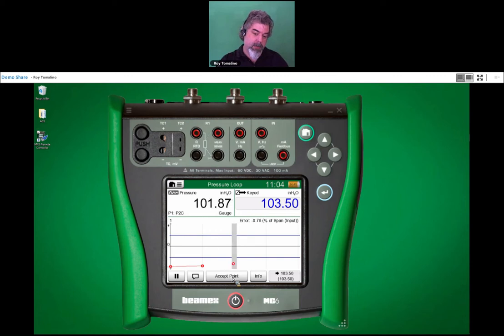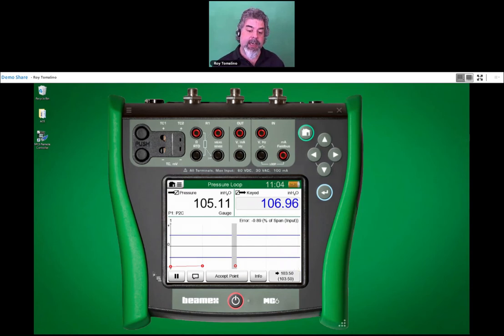So, Ned, I don't know if you can see this, but my test points are red, and I'm thinking that's bad. 106. Yeah, you're bad. You are bad, Roy. 106.96, really? Okay, 106.96, and I'm outside of the blue lines, which is my allowable tolerance. So right now I have 3 failing test points in a row.